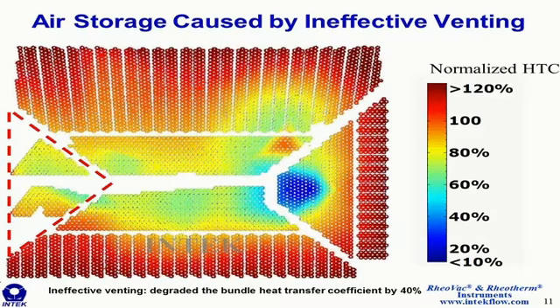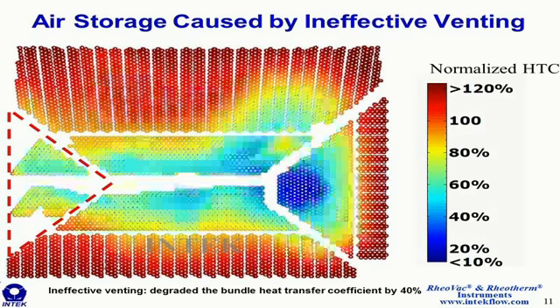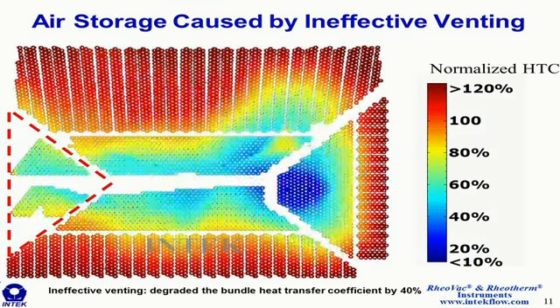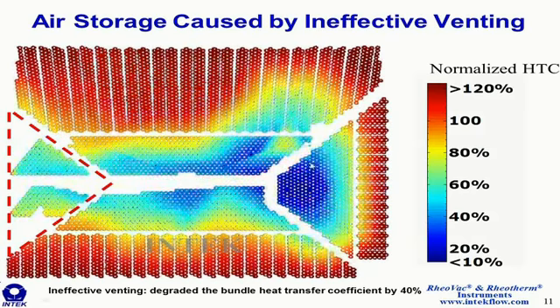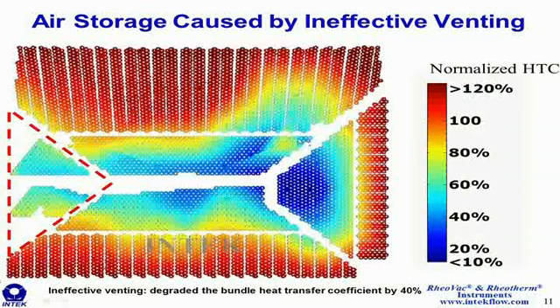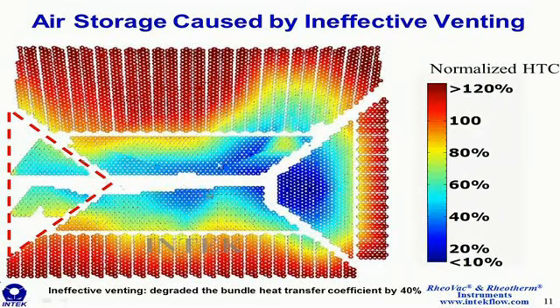So you should start to see the animation creeping along. The outlet tube temperatures are providing us these profiles. You can see now that the central section is now bluer. That small circle of air binding before is now much larger. The stagnant zone has extended into the condenser, joined with that air-bound zone, and the performance profile in front of you now has the heat transfer decreased by about 40% from the original condition. So the way to recover this performance, again, is to decrease the air and leakage or increase the venting capacity.